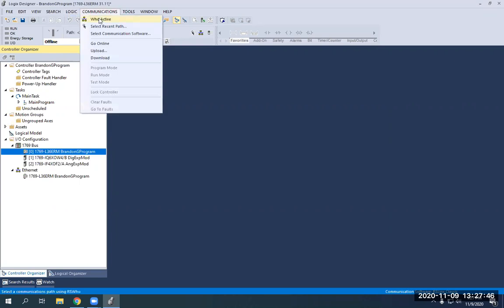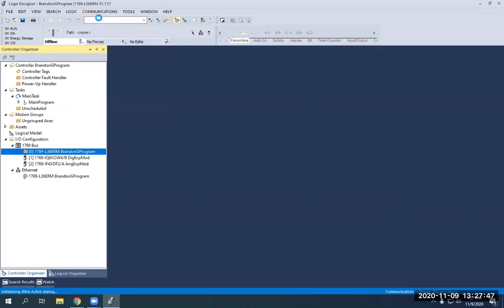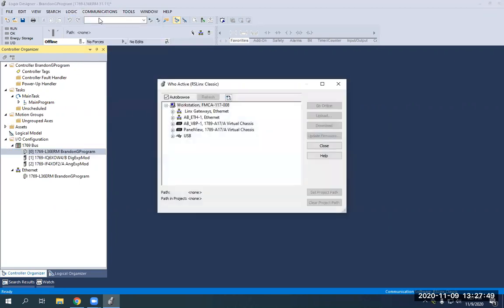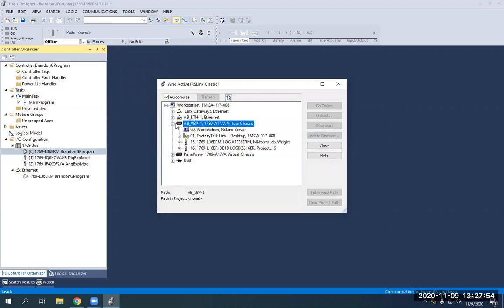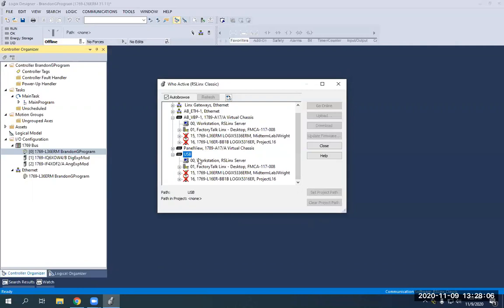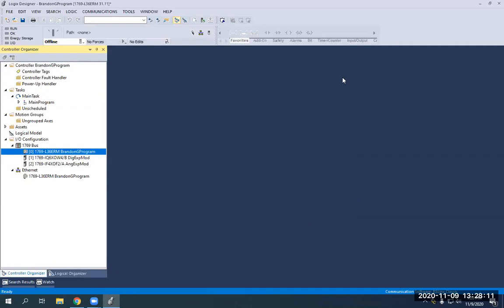So what I'm going to do is go to communication, who active. And then I'm going to find which gate that we want to use. So it's the one that will be connected via USB. Now we're powered on everything, but for some reason it's not showing up here. It would normally be this 1769-L36ERM, and it's not popping up here either. So it's not seeing it yet. So I'm just going to close this and unplug my USB cable and then plug it back into my PC.